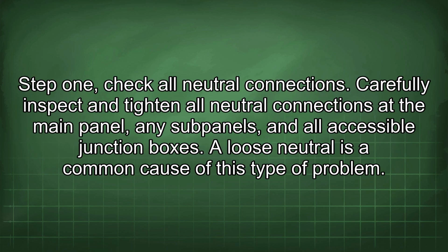Step 1. Check all neutral connections. Carefully inspect and tighten all neutral connections at the main panel, any subpanels, and all accessible junction boxes. A loose neutral is a common cause of this type of problem.